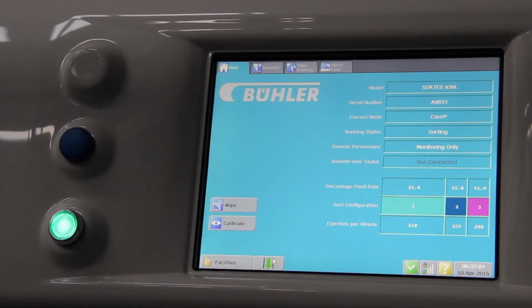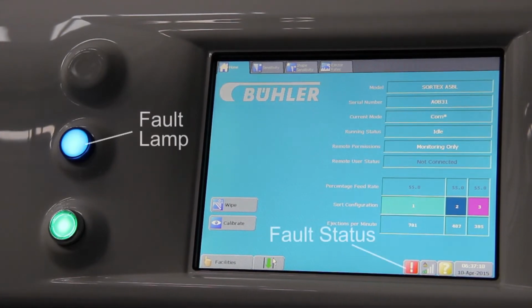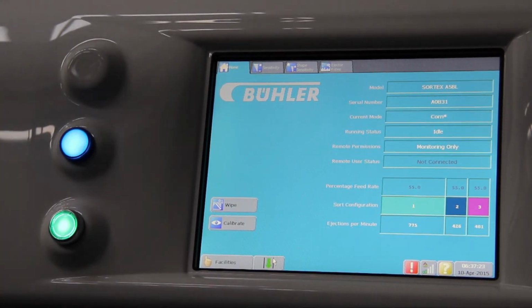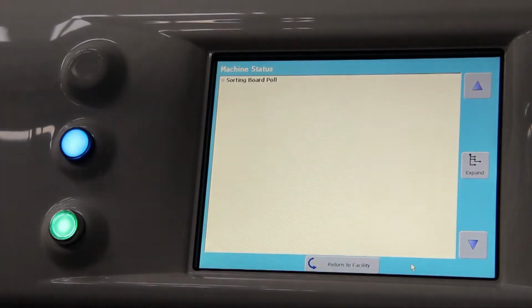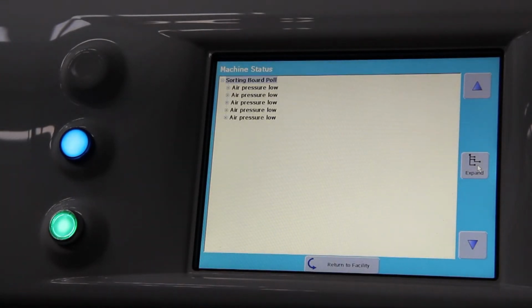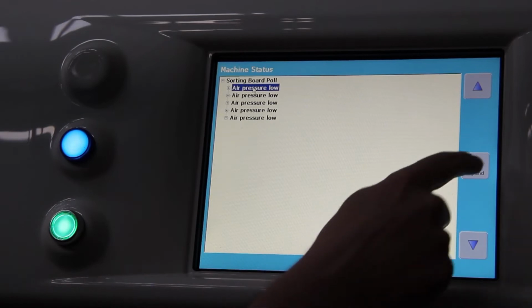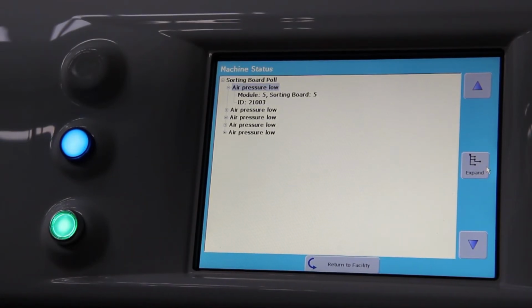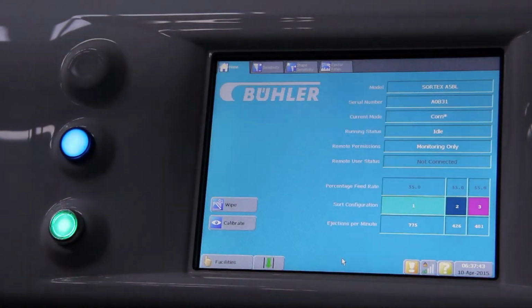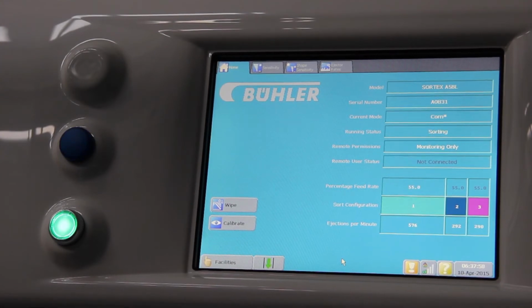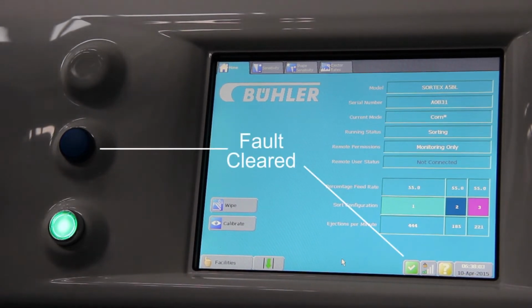If there is a true fault on the machine, the fault warning status icon will indicate by turning red with an exclamation mark, and the fault lamp will illuminate blue. Select and expand to find the cause of the fault. In this case, the air pressure to the machine has gone too low. Returning air pressure to the machine has cleared the fault. The fault lamp is off, and the fault warning status has changed to the green icon.